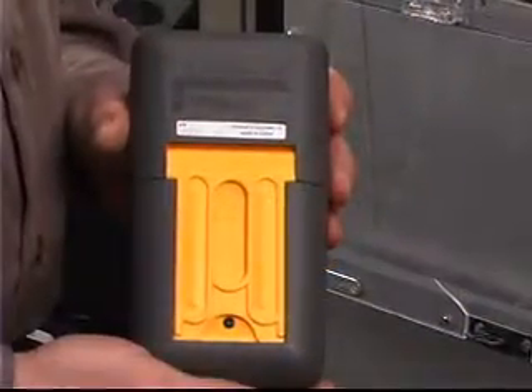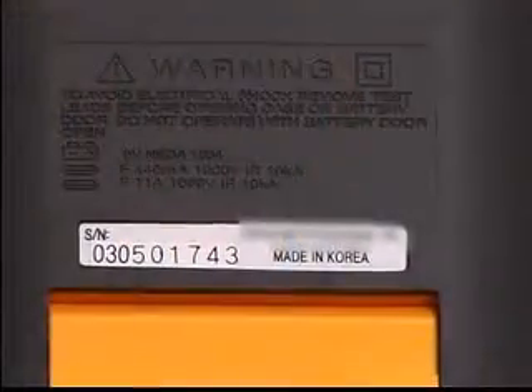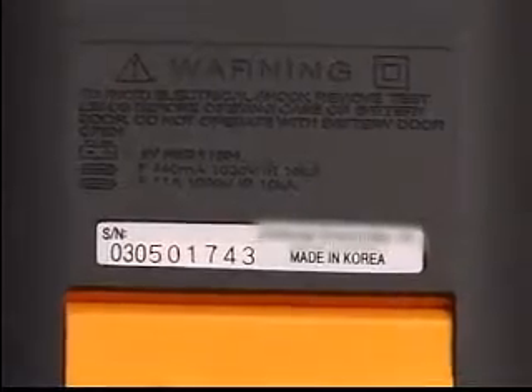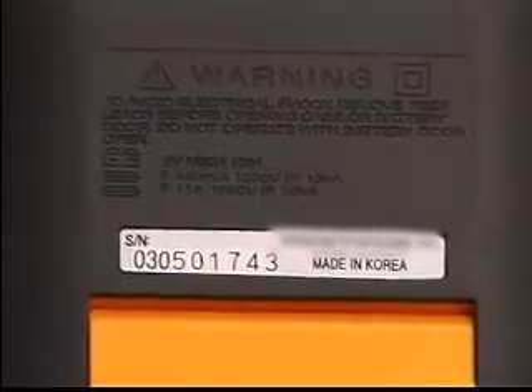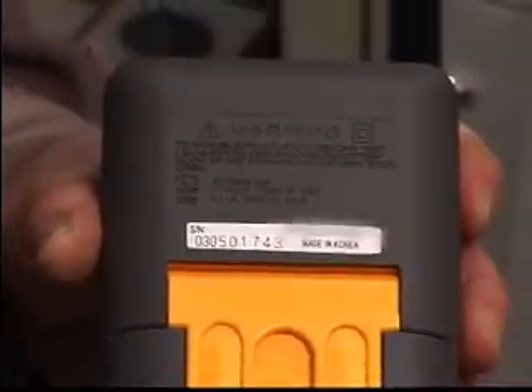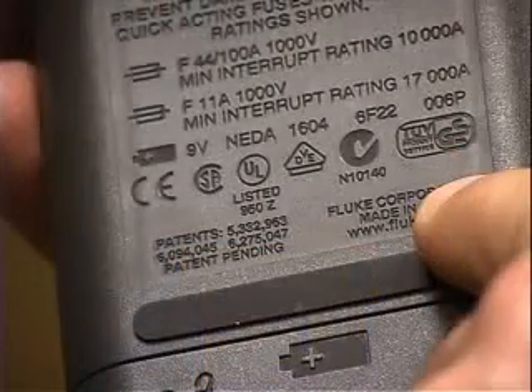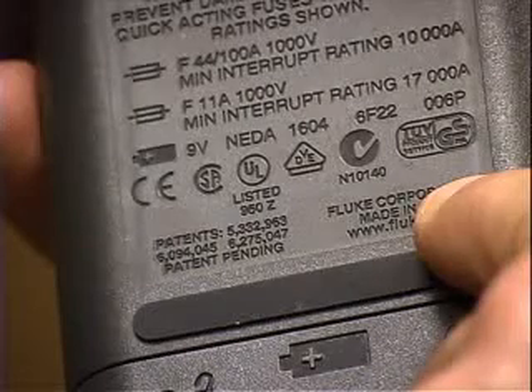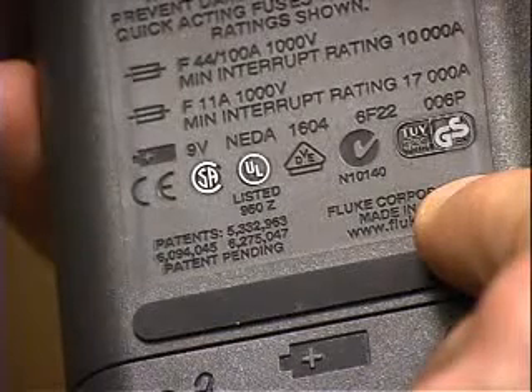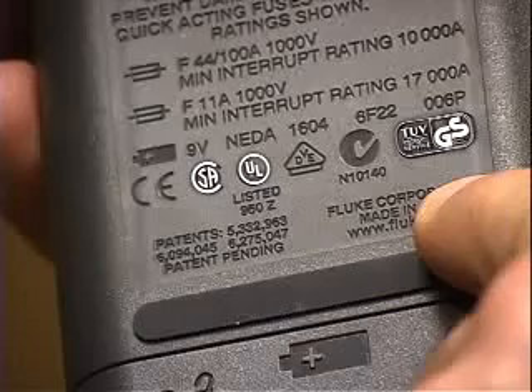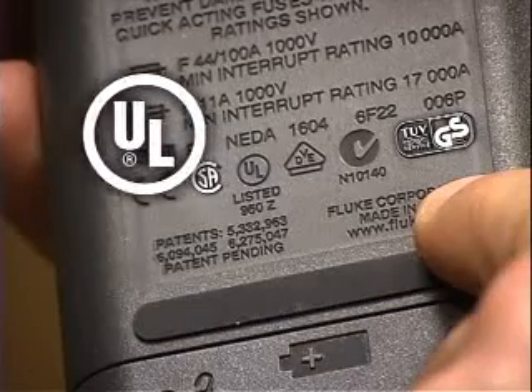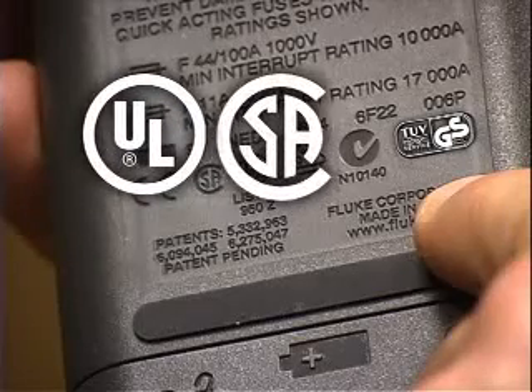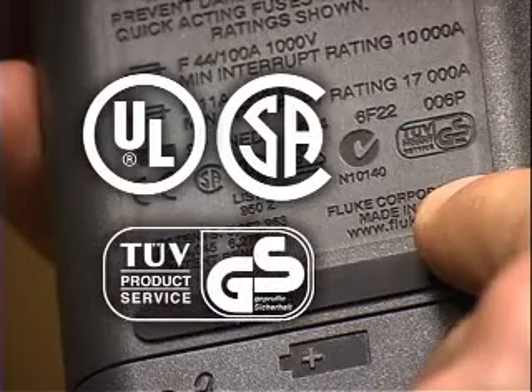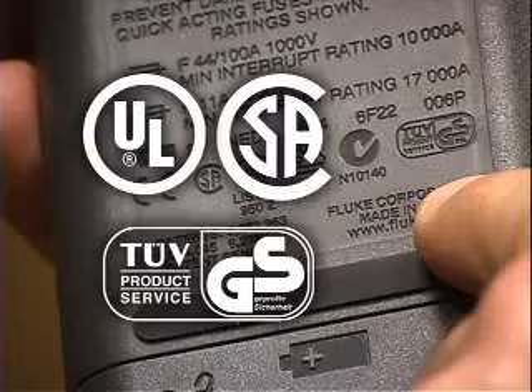How could this meter fail the test? The standards bodies only create the standards. They do not enforce them. A meter that claims to be designed to a standard may have never been tested to it. That's why it is essential that the tester you use is labeled to show it has been certified by 2 or more independent testing laboratories, such as UL in the United States, CSA in Canada, and TUV in Europe.